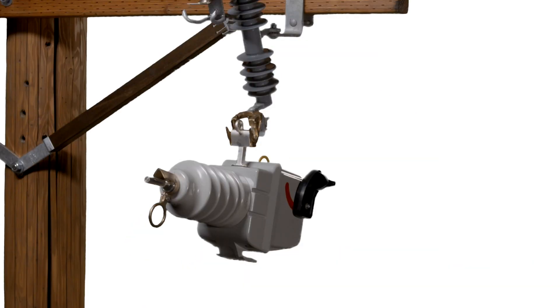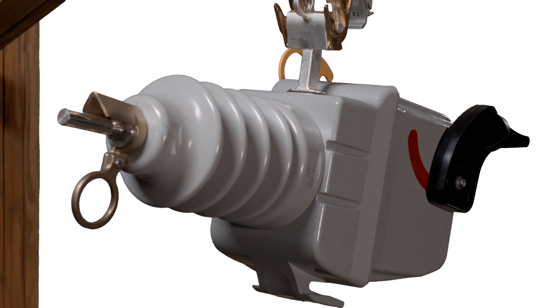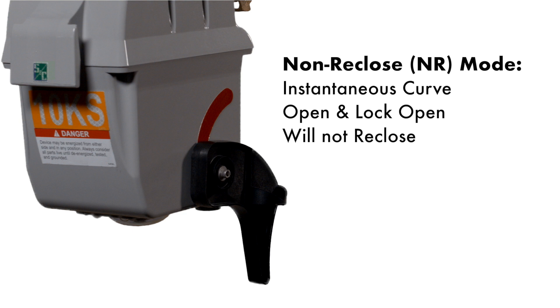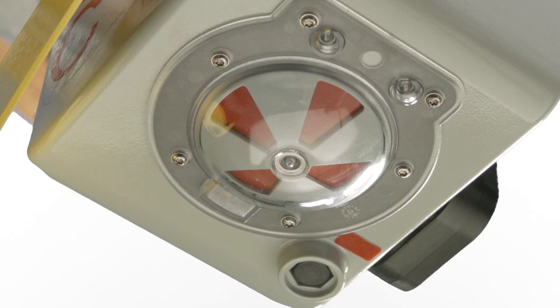The mode selector lever can be in the up or down position depending on the desired behavior of the VacuFuse Interrupter after closing, and its exact function will be discussed later in this video. Regardless of the position of the mode selector lever, the interrupter will operate in non-reclose NR mode for the first 10 seconds after closing and energizing. Non-reclose mode uses the instantaneous version of the interrupter's TCC curve. If a fault is present on the line within the first 10 seconds, the interrupter will open and lock open.